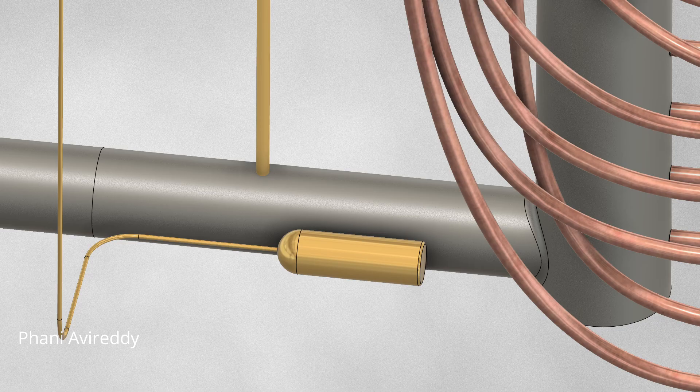At the same time, pressure from the equalizing line acts below the thrust piece, pushing it upward. It is important to note the distinct roles of the equalizing line and the sensing bulb. While the equalizing line is connected directly to the evaporator outlet to sense pressure, the sensing bulb is only in physical contact with the evaporator outlet to detect the temperature of the refrigerant gas flowing through.